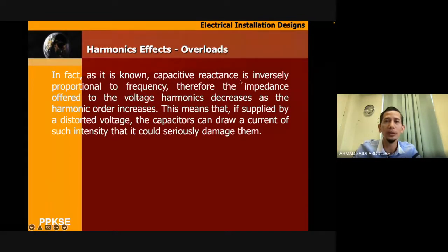And then capacitive reactance is inversely proportional to the frequency, therefore the impedance offered to the voltage harmonic decreases. This one explains how the process happens. Okay, capacitive reactance is inversely proportional to the frequency, therefore the impedance offered to the voltage harmonic decreases as the harmonic order increases. This means that if supplied by a distorted voltage, the capacitor can draw a current of such intensity that could seriously damage them. So that is the issue related to the harmonic.